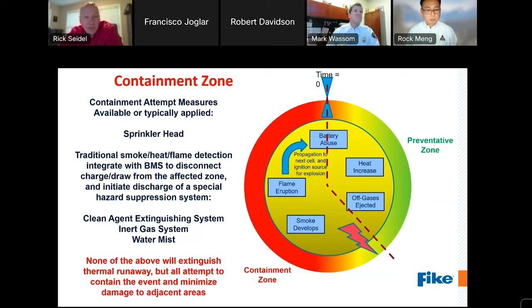Most energy storage units do come equipped with some form of traditionally common fire protection approaches, a typical spot type smoke detection and/or a sprinkler head being most common. On occasion, they may come equipped with a clean agent fire suppression system. Unfortunately, by the time either of those systems are activated, the thermal runaway is likely already underway and well involved, and neither of those types of systems will stop or extinguish thermal runaway once it has started. In this case, they are only there to attempt to minimize the damage and protect the surroundings of the overall energy storage unit itself. Next, please.